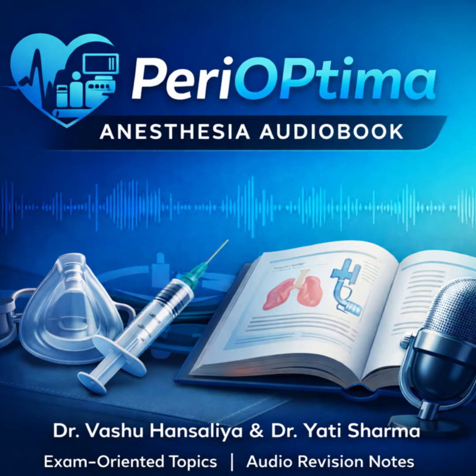Okay, so let's break that down. Systems without an absorber, which you can think of as non-rebreathing systems, rely completely on high fresh gas flow, or FGF, to physically flush the expired carbon dioxide out of the system before the patient takes their next breath. This category includes all the Mapleson systems A, B, C, D, E, F, and modified versions like the Bain circuit. But, and this is a key point, they are non-rebreathing circuits only if the FGF meets or exceeds that necessary washout flow.